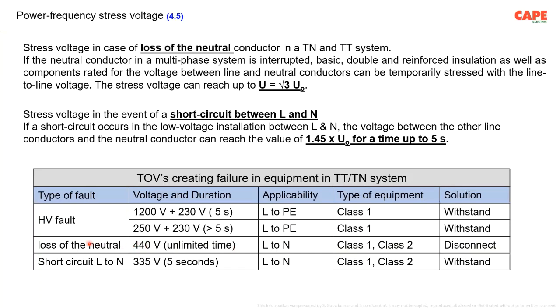But technically speaking, in an industrial installation, this kind of a situation is very, very rare. Of course, for public distribution, especially public distribution overhead line, this condition is quite normal. Also in public distribution, if the joints are not proper, then such problems are expected. The third issue, short circuit between line to neutral. Please note that this is applicable between line to neutral. The first two are between line to earth. The third one is between line to neutral up to 335 volt for 5 seconds. You can expect a temporary over voltage between line to neutral, both for class 1 and class 2 equipment. And here your equipment must be able to withstand the stress voltage.